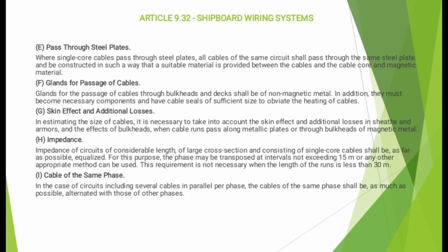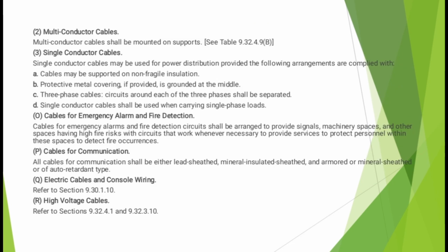Cable of the same phase. In the case of circuits including several cables in parallel per phase, the cables of the same phase shall be as much as possible alternated with those of other phases. Multi-conductor cables. Multi-conductor cables shall be mounted on supports. Single conductor cables. Single conductor cables may be used for power distribution provided the following arrangements are complied with. A. Cables may be supported of non-fragile insulation. B. Protective metal covering, if provided, is grounded at the middle. C. Three-phase cable circuits around each of three phases shall be separated. D. Single conductor cable shall be used when carrying single-phase load.